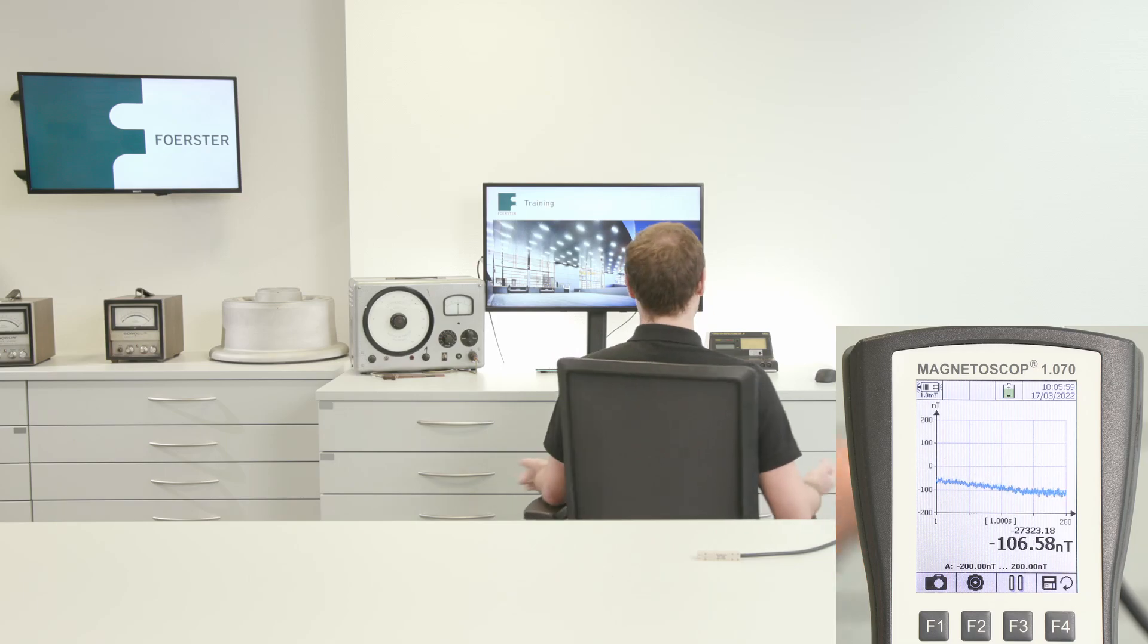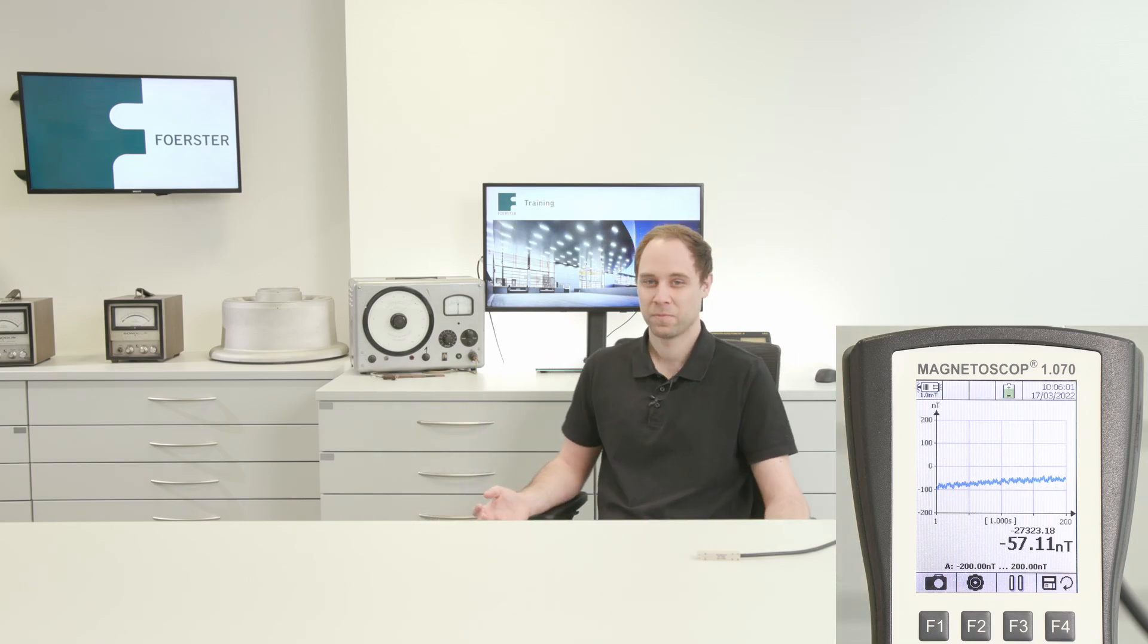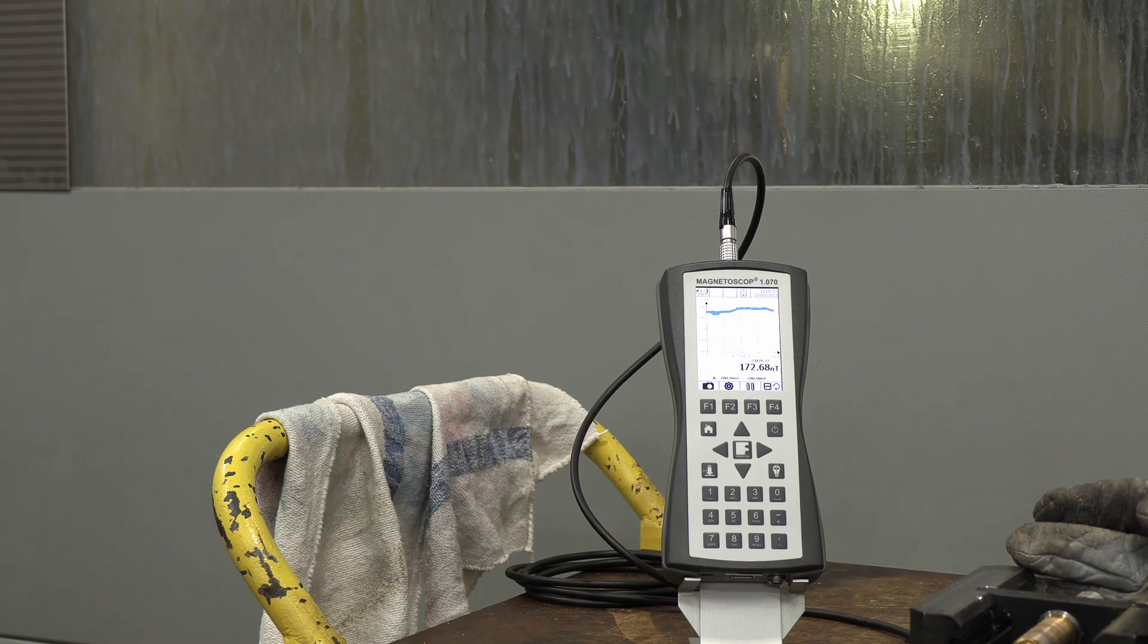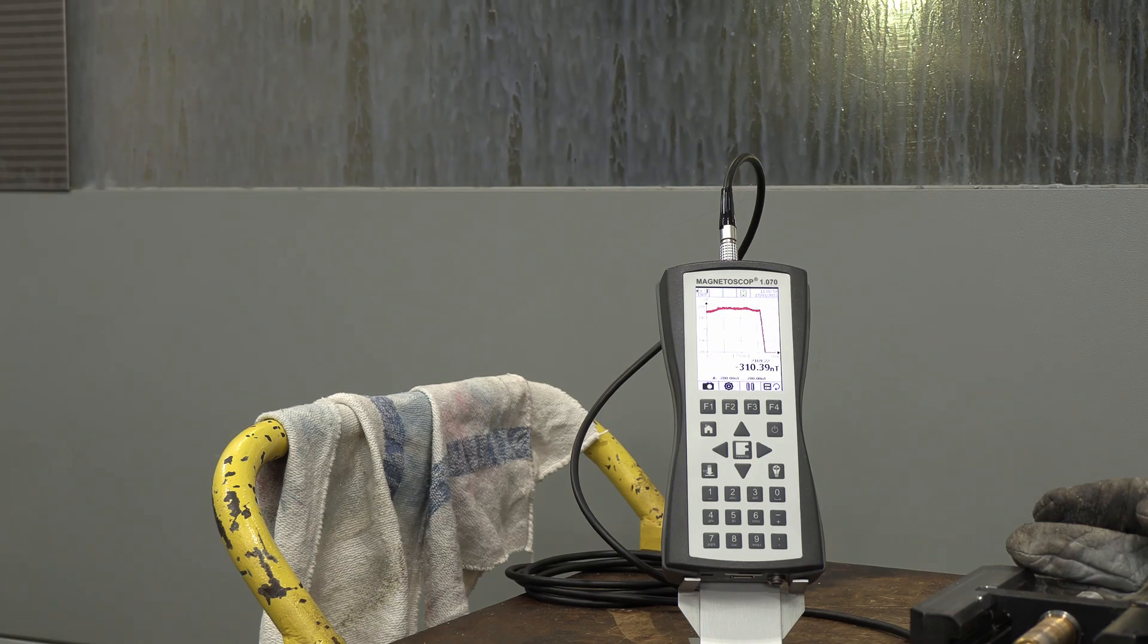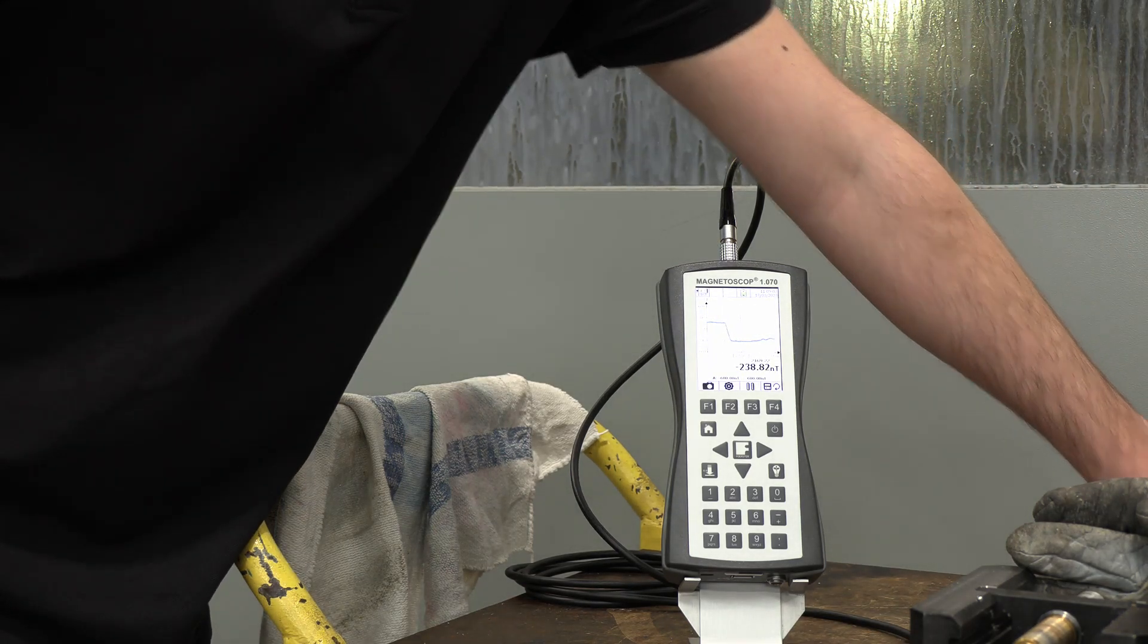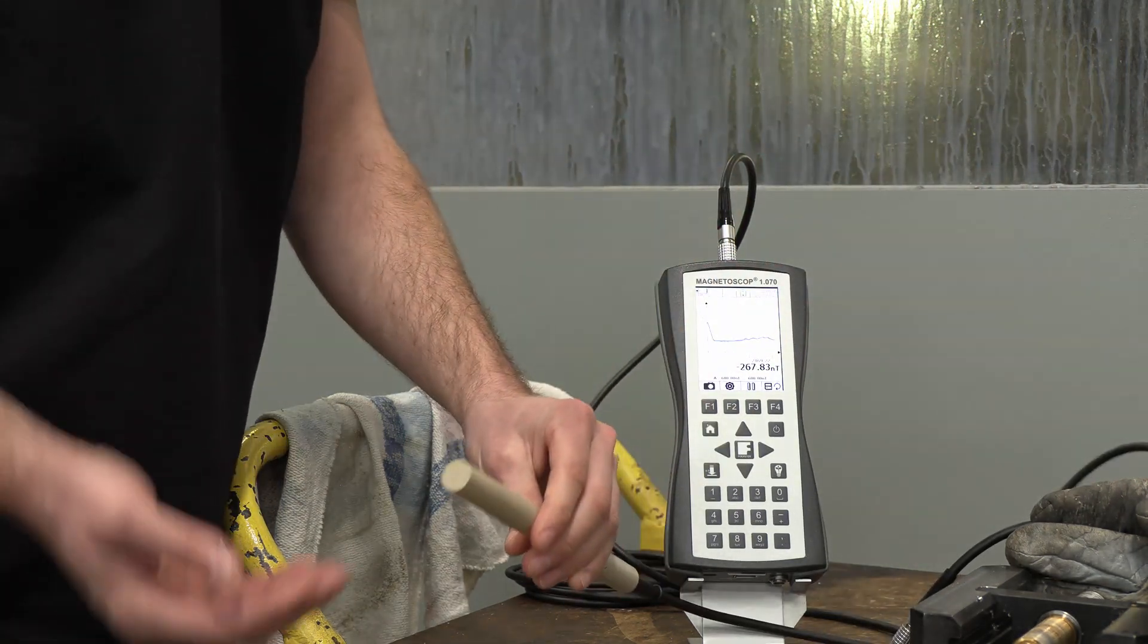Don't move around with chairs, and don't position your measurement station close to large machines like this milling machine. To reduce disturbing fields, a differential probe can be used.